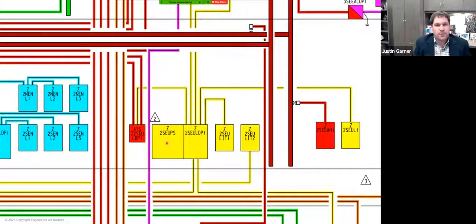And so what you're normally going to see is some type of UPS. Typically, your networking systems are almost always served by a UPS, or uninterruptible power system, which is basically a battery backup so that you never have a blip. It will seamlessly switch from battery power through an inverter over to the utility or the emergency source that's feeding it. And that's what we have here in this particular instance. We have an ATS that's actually fed by two emergency sources, feeding into a UPS, which is this module here with its own distribution panel.